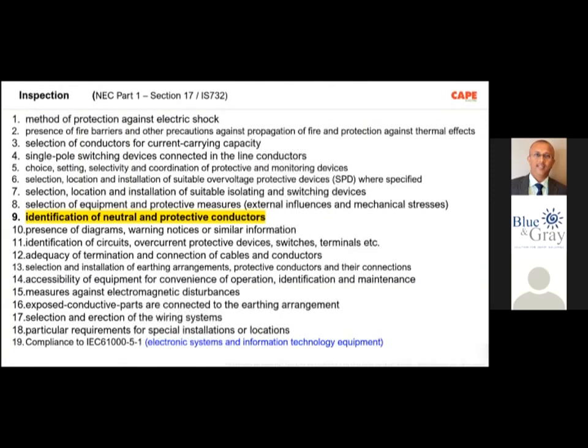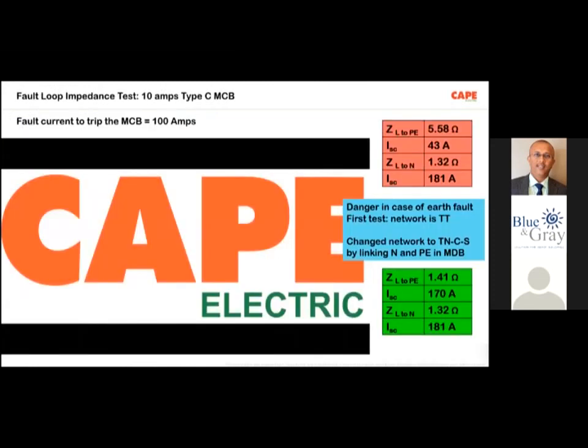Now, going back, what exactly is the installation test? One more point from the previous slide: I have shown you this test is required for an electrical machine. This test is required for a lift, for example, an elevator. To my knowledge, the only lift company doing this test is Schindler, a Swiss company. They do this test in every electrical installation and they ensure that the MCB is tripping.